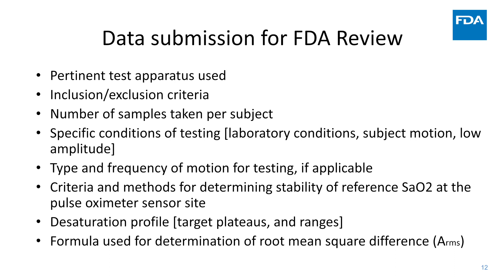So during the analysis of a pulse oximeter that's derived from pooled data pairs, all subjects within the entire test range, typically 70 to 100%, are considered. Currently clinically relevant thresholds like 94% or 88%, or the range 86 to 94%, let's say, are not analyzed further. Importantly, the study is not particularly powered to determine significant differences between cohorts, such as age, sex, or specific pigmentation values.